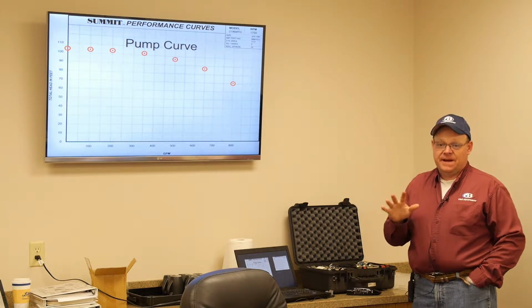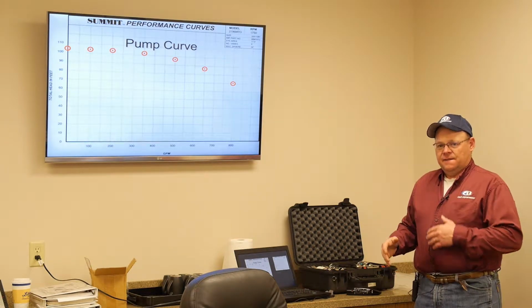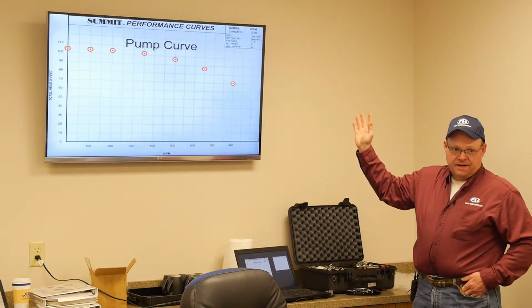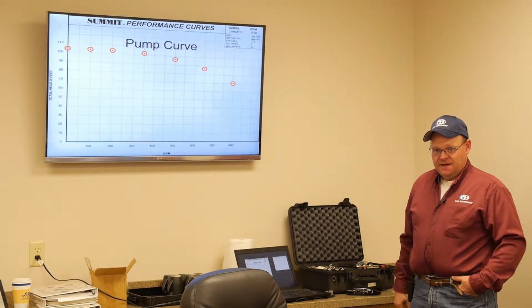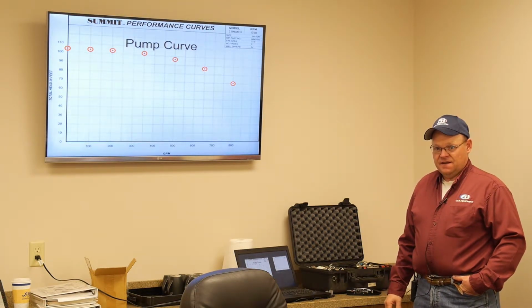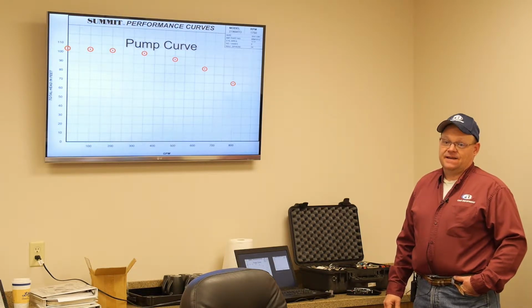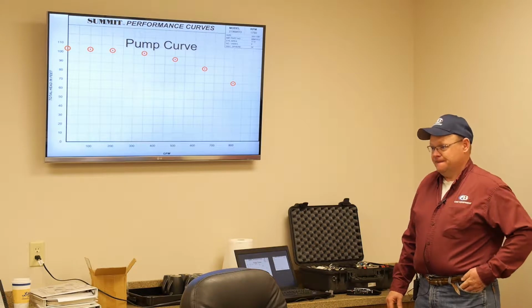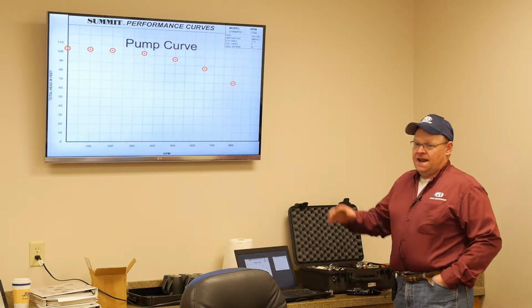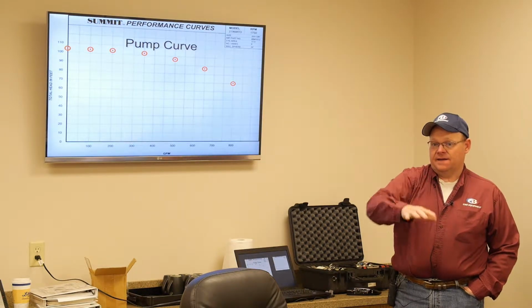So just 15 pounds doesn't seem like much when you're talking about a pump that'll go from 45 to 30. You could take 15 pounds off the discharge or add 15 to the suction, and it would do the same thing? Do the same thing, exactly. Exactly. And you bring up an excellent point.